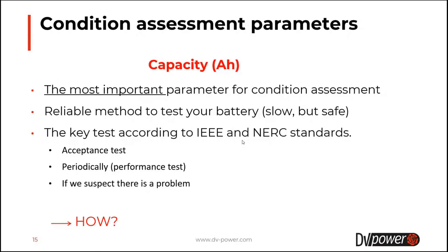It is a part of the acceptance test, which is the first test when installing a battery. A capacity test is also a part of periodical testing, a performance test that needs to be done annually or every 25% of expected battery lifetime, whichever is less, or if we suspect any problem with the battery. As I already said, if we perform the internal resistance test and suspect a problem, it is good to verify that by performing a capacity test. And now we will show you how to perform a capacity test.